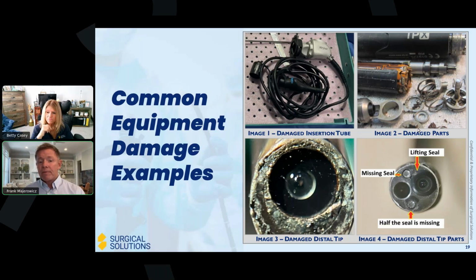And that is something that's very common. I can tell you from experience, I could walk into any facility today and look through a dozen scopes, I'm sure I could find 1 or 2 that have seals that are either completely missing or half missing. And I point that out as a potential cleaning hazard, and not to scare anybody with that word, but it really can be a potential cleaning issue. And those are things that should be routinely looked at and taken care of in a timely fashion.